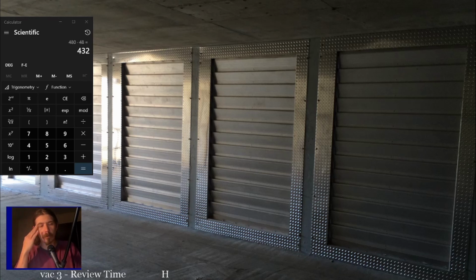All right, I would read all of 4.4 a couple times to make sure you've got a good grasp, because textbook ways of electrical troubleshooting are extremely important concepts to have down, and probably the most common thing that guys who just aren't very good at troubleshooting get wrong. Troubleshooting voltage to ground all the time is a bad idea because it can get you into trouble. Not using the hopscotch method of going through a control circuit, which we talked about a little bit in one of the first classes on this module, is a bad way of getting yourself in trouble because you end up thinking something's wrong that's not wrong.